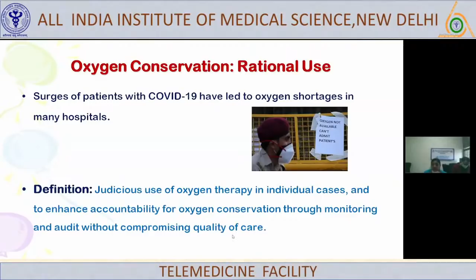They can inspect the oxygen source in each shift. We should check the wall mounted outlets and also the cylinders, that there should not be any leakage, and closure of the valves in the pipeline system in no-use areas has to be done. If wall mounted oxygen is there, sometimes we can see the valve is open, so that has to be periodically checked in each and every shift in wards as well as in emergency departments, and closed whenever required.